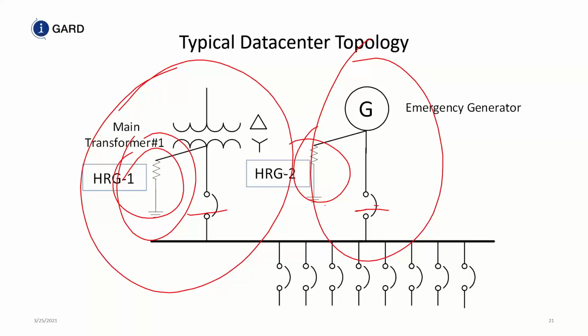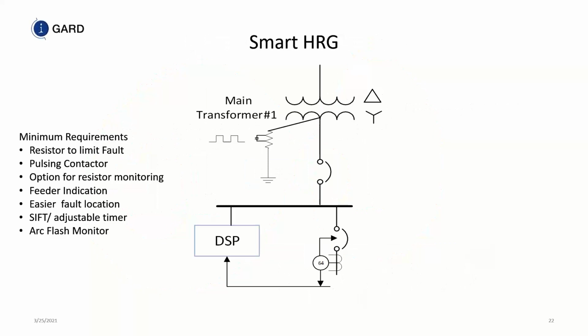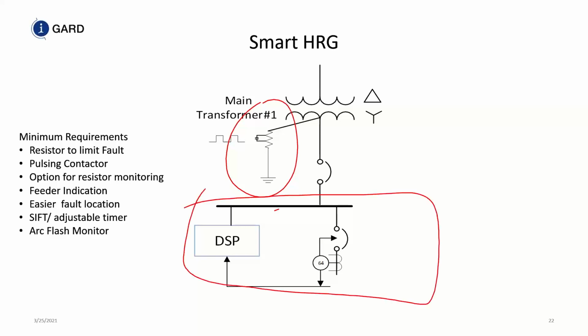Because normally the utility transformer and the generator are not in the same building. But if you had a smart high resistance grounding system, we go a step further. You still have the resistor over here in the pulsing contactor, but we're able to detect if you have a fault by monitoring the voltage on the bus. And if you can monitor the voltage on the bus, it doesn't matter where the fault is. The fault is always going to be in the loads. If the fault is in the loads, we tell you what load or what feeder that fault is in. So we give you feeder indication. It's easier to find the fault because I tell you where to begin looking for the fault.